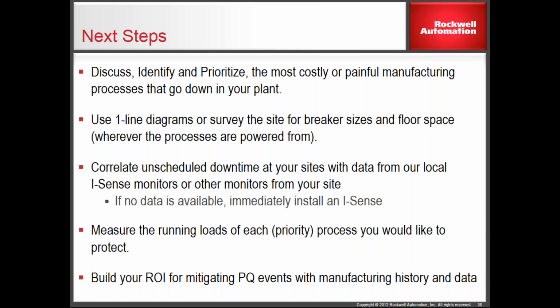Because now you can look at a diagram and say, you know what? There's 4 of these right here that have to be protected, and they're all fed out of this same bus. So I could put one, maybe a 400 amp unit up here, instead of putting 4 100 amp units down there. It's going to cost you less money per amp to protect it that way. You're only going to do 1 install instead of 4, right? And all the rest of the equipment on that bus is protected anyway. So your power supplies will last longer, and your drives will last longer, and you get a lot of secondary benefits. But it starts out by protecting the pain points.